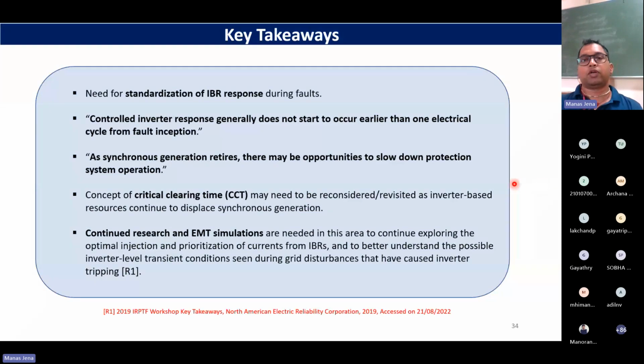So with these discussions related to protection, what are the key takeaways from this? We need to standardize the IBR response. Standardize the IBR response. That means all the inverters, all the farms, inverter generating stations should comply with the grid code very strictly. Because I will be able to set my protection correctly if I know that definitely the response from the inverter will be like this during fault. That is how protection has been operating very nicely, very reliably for the last 100 years or so, because we know that this is how the voltage source will respond to a fault. But now I need to standardize the IBR response during fault. Definitely this is the signature I am expecting, then I can design the protective algorithm.